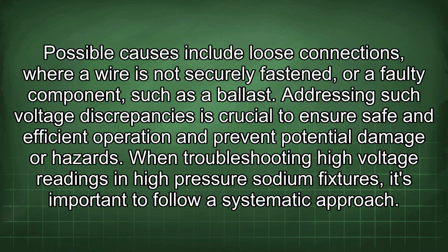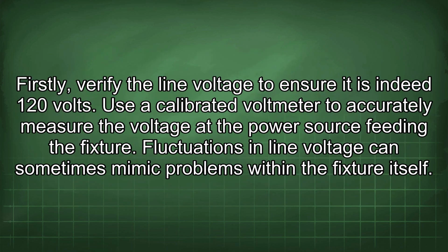When troubleshooting high voltage readings in high-pressure sodium fixtures, it's important to follow a systematic approach. Firstly, verify the line voltage to ensure it is indeed 120 volts. Use a calibrated voltmeter to accurately measure the voltage at the power source feeding the fixture. Fluctuations in line voltage can sometimes mimic problems within the fixture itself.